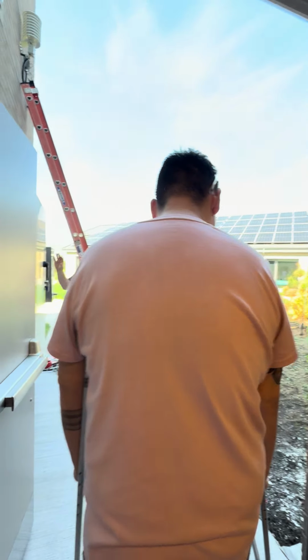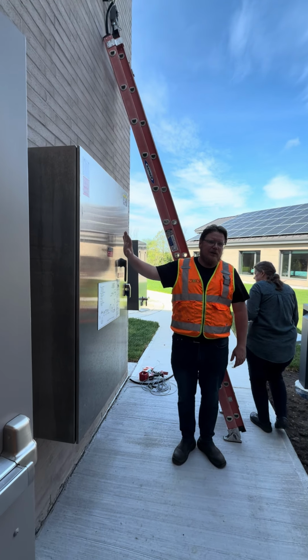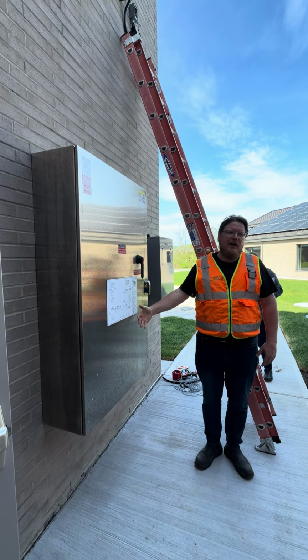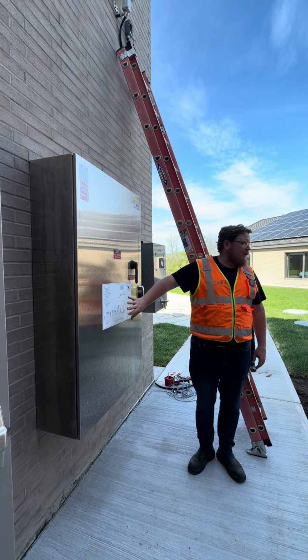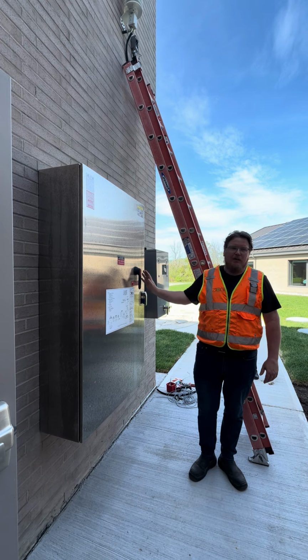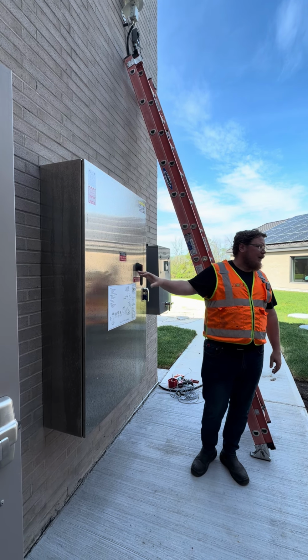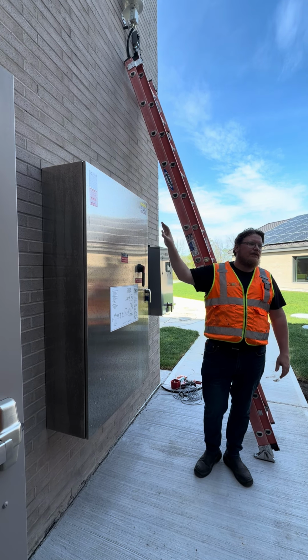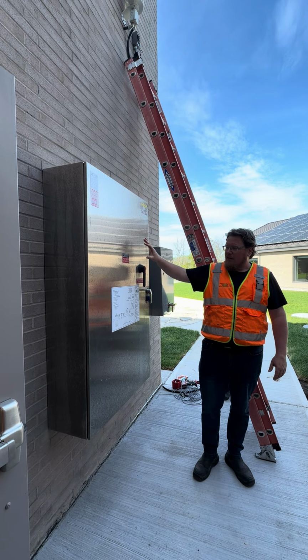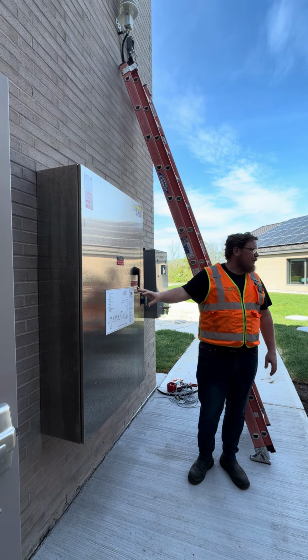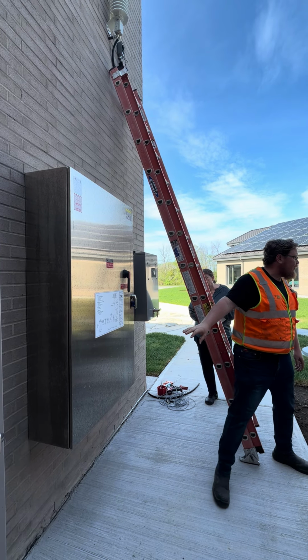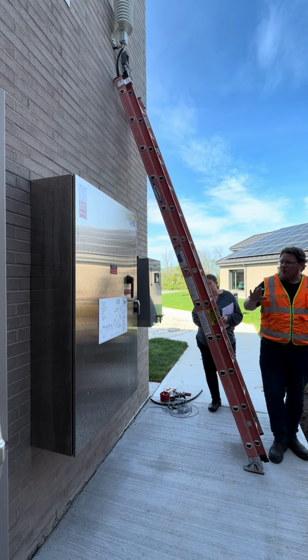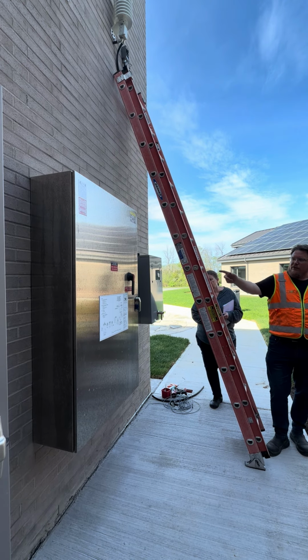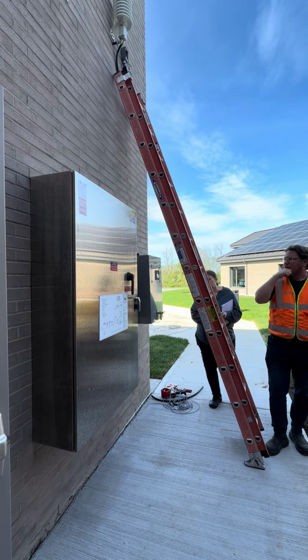So all that power gets combined and it comes, I won't open this because this is live and there isn't a dead front on it. All that power gets combined and comes into here. This is the emergency disconnect. So if there ever was an emergency, this is the switch to turn it off. I'll show you another softer way to turn it off if you need to, but this is essentially the utility isolation. So if there's an emergency at the building and they need to isolate the solar, this is the disconnect switch that they'll turn.